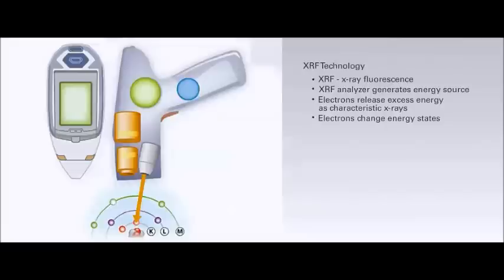At the same time, this electron releases energy to move to a lower energy state. The fluorescent energy release then travels back through the XL3's Kapton window and into the instrument's high-resolution x-ray detector.